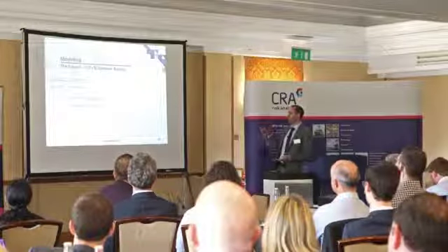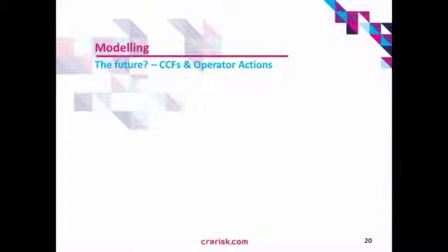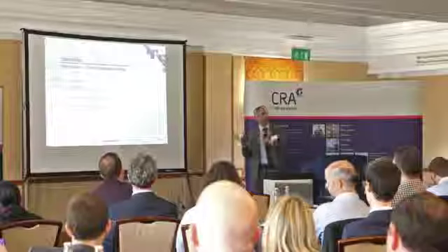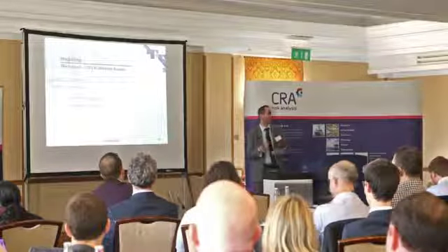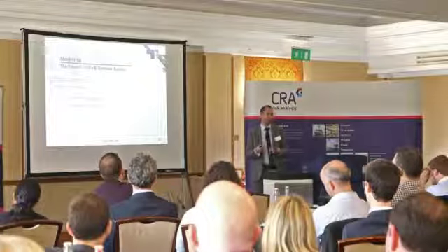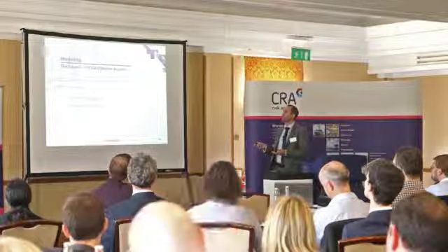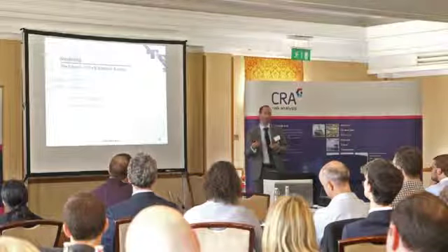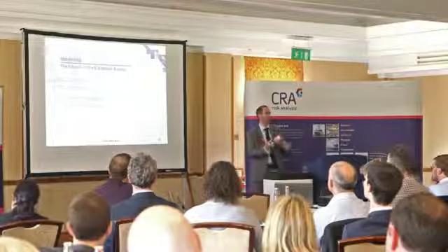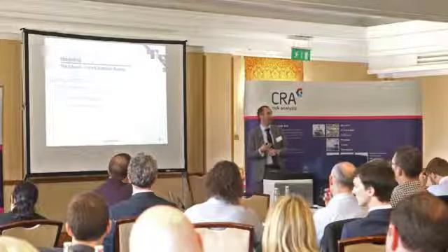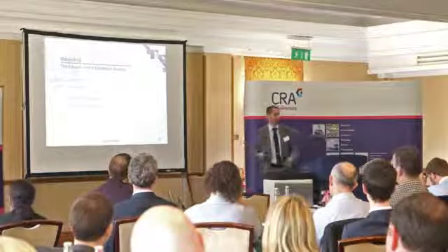I thought this up on a day when I was thinking a lot about seismic, but it turns out I'm not the first person. There are a few papers where they have actually done seismic CCFs using the old beta factor model. And they've adapted the beta factor to take account of seismic similarities between the components. Currently, what's out there at the moment, from what I understand, is they are looking at actually doing proper deterministic assessments of the plant and giving you essentially like a beta factor as to how similar bits are. And you pay a seismic specialist probably an extortionate amount of money to do that across all your components.